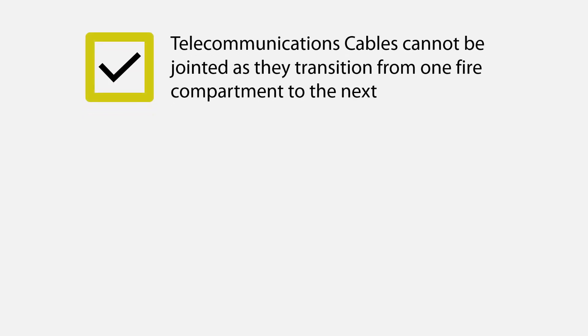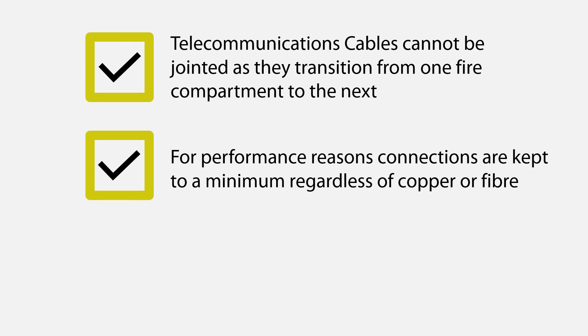Once more for further clarity, unlike electrical cables, with telecommunications cables, connections or joints must be kept to a minimum as each one will introduce an unwelcome signal loss. Therefore, telecommunications cables must be of the same Euro class as they transition between fire compartments. Also, consider what the evacuation route or space means — it is effectively any space within a building that a human can occupy.